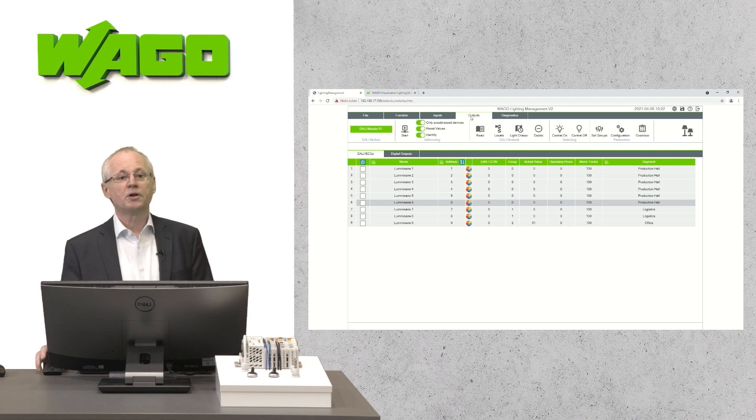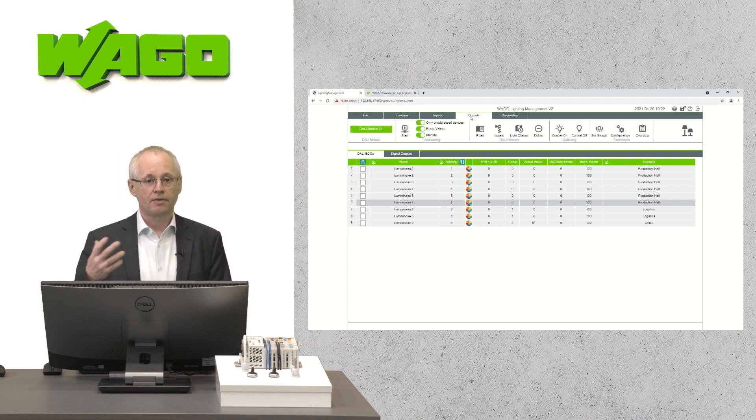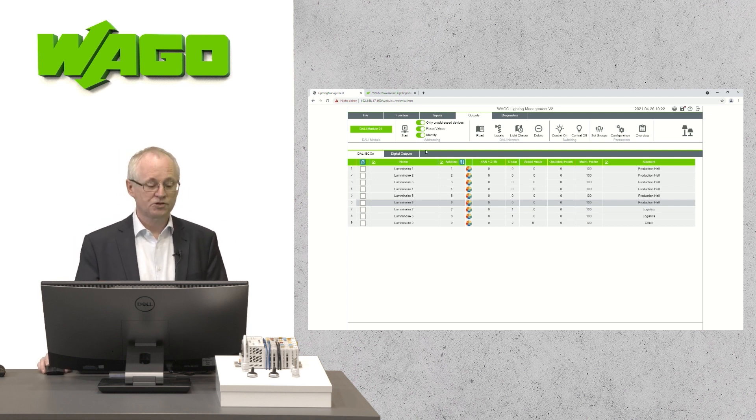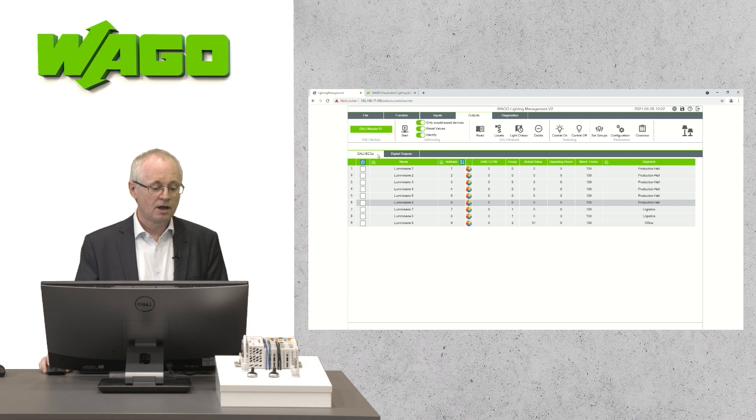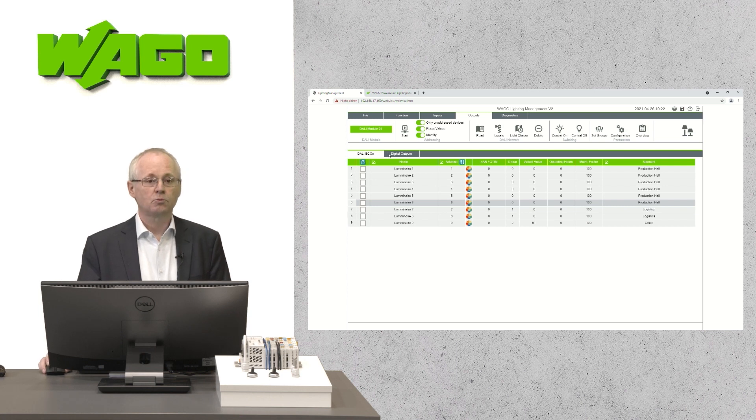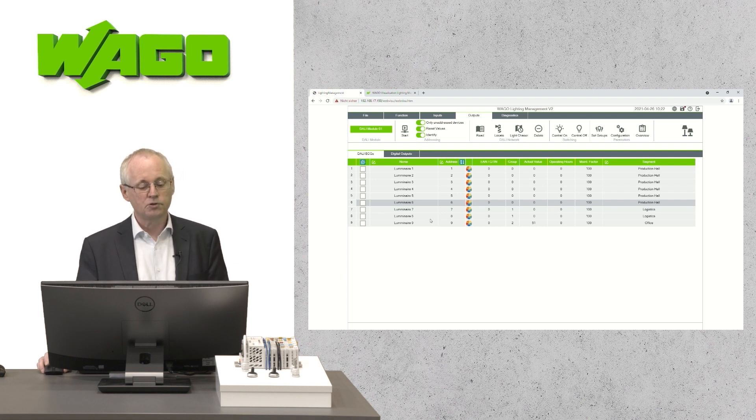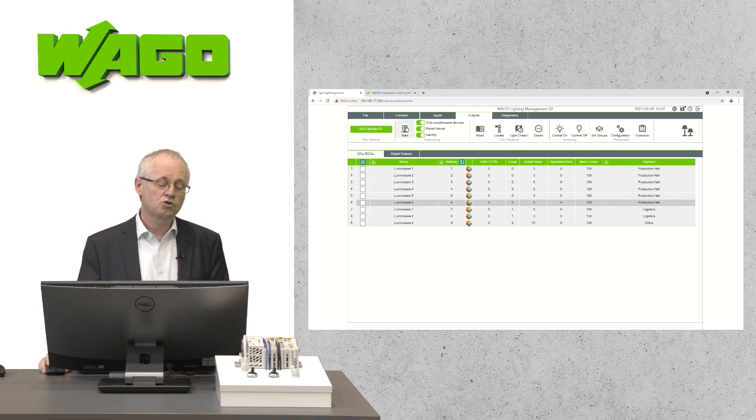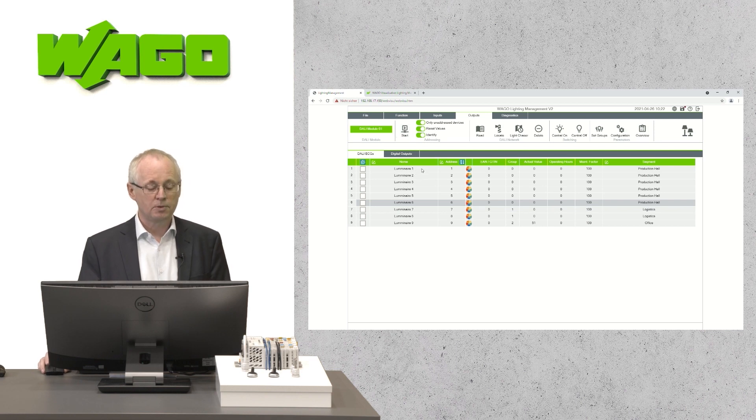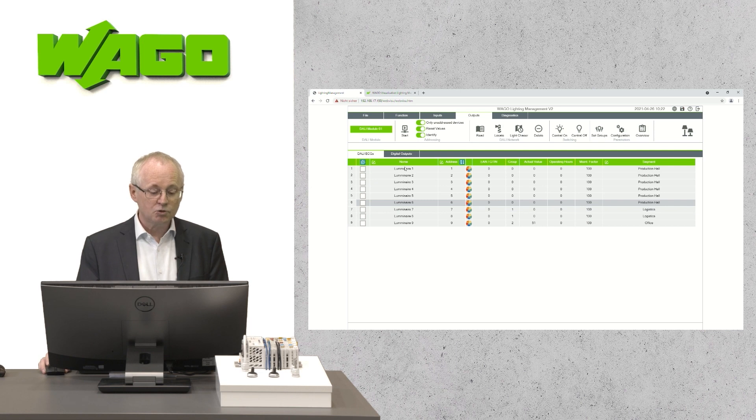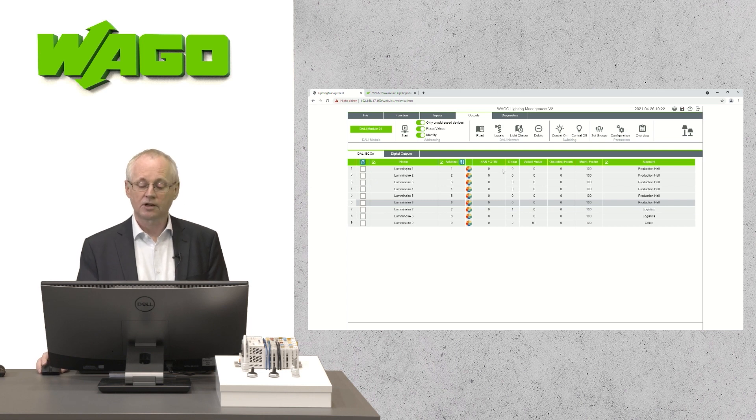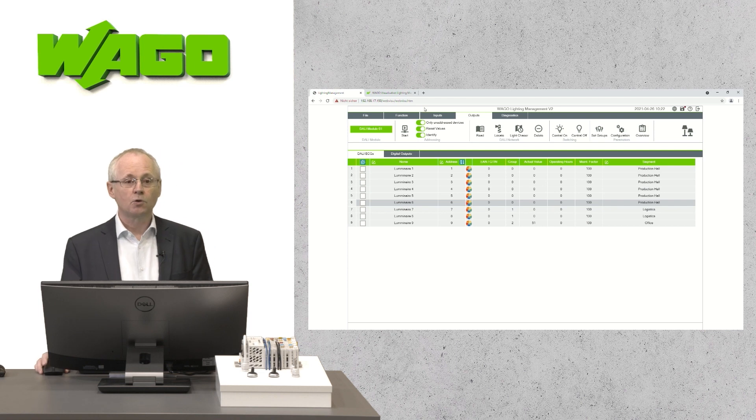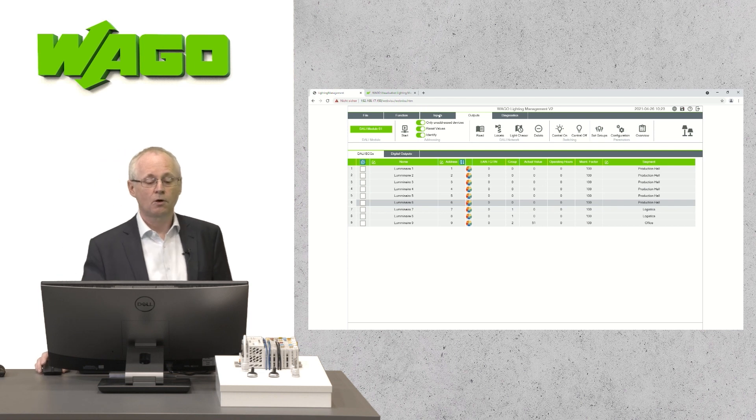Now the outputs. The outputs will be configured in the same way. There are two possibilities via DALI and via digital outputs. You can see that there are already some luminaires configured here. Also here, in case of a new configuration, you will start the push button and all connected luminaires will be listed here. You can assign a name to each luminaire and assign the luminaire to the segment.